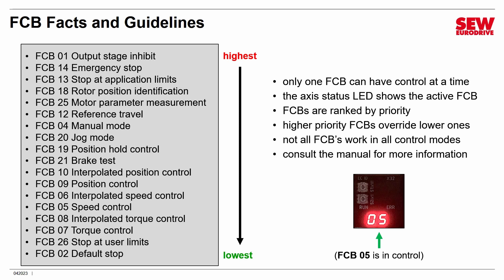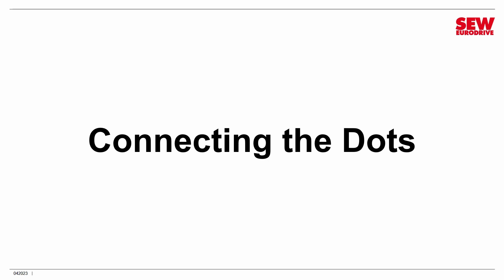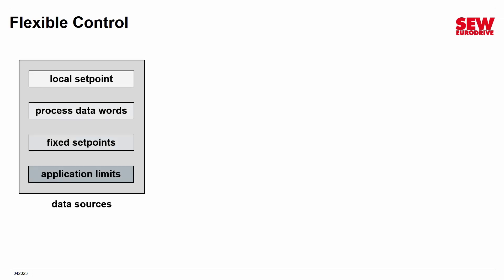If you want to know more about FCBs, take a look at the manual — there's a whole section on them. Now, what about connecting the dots? FCBs do the work, but they have to get their information and guidance from somewhere. This is why the Movi-C product is so incredibly flexible, because the ability to connect the dots is extremely flexible. We have multiple places you can get data to feed the FCBs: there can be local setpoints and fixed setpoints you set up in the VFD, process data words coming over a fieldbus from a controller or PLC, and various kinds of application limits that keep things within constraints.